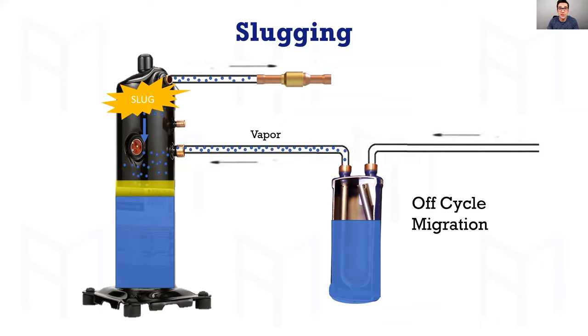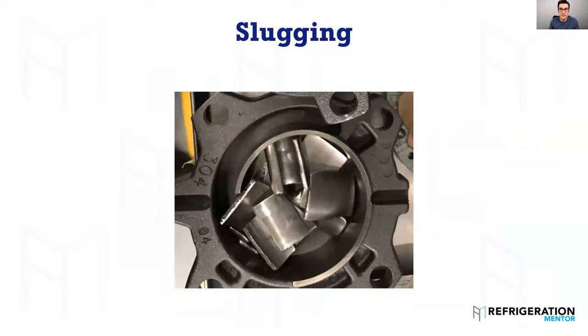A major flooded start causes slugging in scroll compressors. This is what it looks like when you cut one open. To open a scroll, you really need to seal it down to a table or pallet, wear glasses and a safety shield, and use a reciprocating saw — some people use a grinder or even plasma cutters. I've cut dozens of them open. This is a compressor that took a slug — it could be from oil or liquid refrigerant — but you need to understand what caused the failure. Until you start cutting more compressors open and looking inside them, that's when you're going to start learning more.